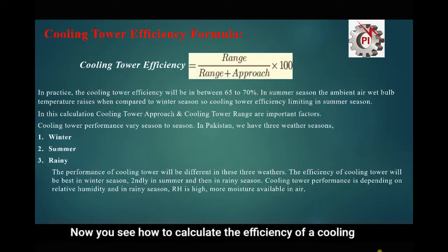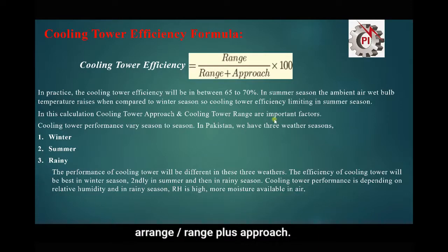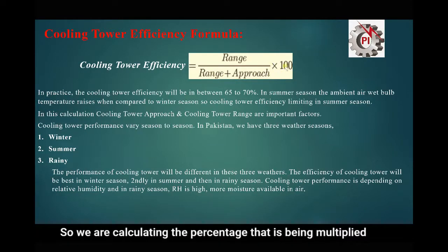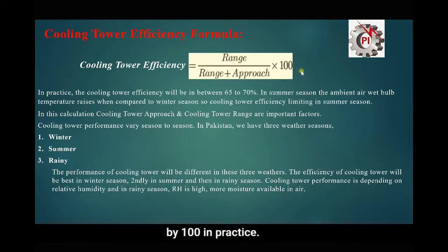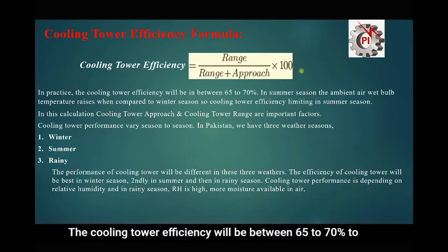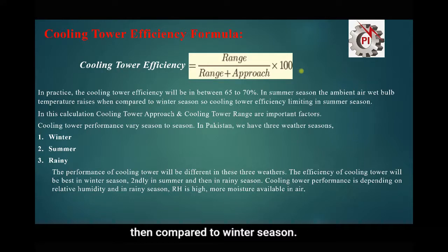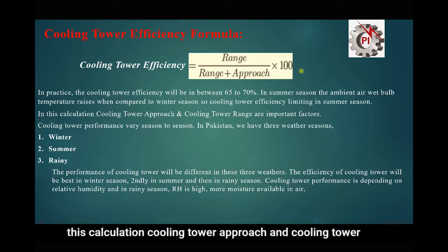Now we will see how to calculate the efficiency of a cooling tower. The formula is: Efficiency = Range / (Range + Approach) × 100%. In practice, the cooling tower efficiency will be between 65 to 70 percent. In summer season, the ambient air wet bulb temperature rises compared to winter season, so cooling tower efficiency is limited in summer.